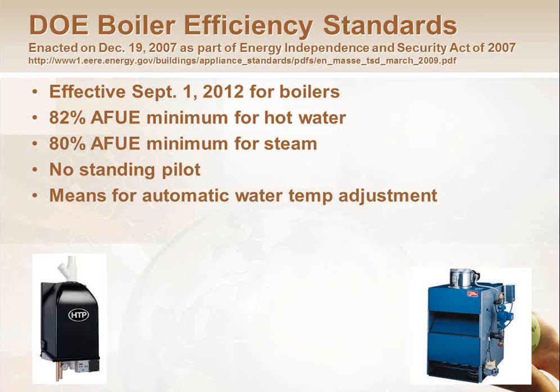And then the most important one out of that, that has been the biggest stumbling block for some of the guys who do these smaller boilers and the residential boilers, is that you have to have a means for automatic water temperature adjustment. For most of us, that means outside air reset schedule. That's built into a lot of boilers anyway, and if it's not, it's easy to get. But that's not the only way to do it. There are other mechanisms. I know the boiler down on the right-hand side in that picture, the Utica one, they're working on a method of staging their boiler, based on temperature differentials and things like that. But for the most part, it means you have to have outside air reset as part of your boiler. That's for boilers smaller than 300,000 BTUs. Larger boilers are not subject to this particular rule.